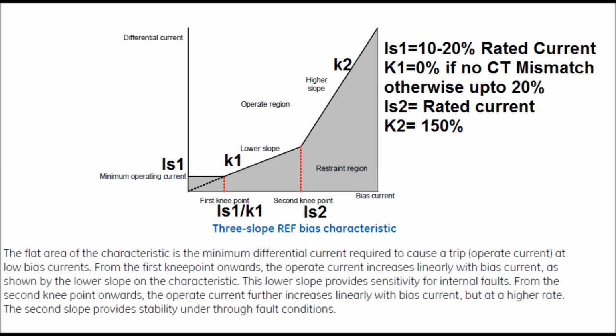The characteristics of a low impedance REF relay are shown in this diagram. Here ID, or differential current, is represented on the y-axis, and the bias current is represented on the x-axis. The flat area of the characteristics is the minimum differential current required to cause a trip signal for low bias current. Here IS1 is the minimum operating current, which is set as 10 to 20% of the rated current.